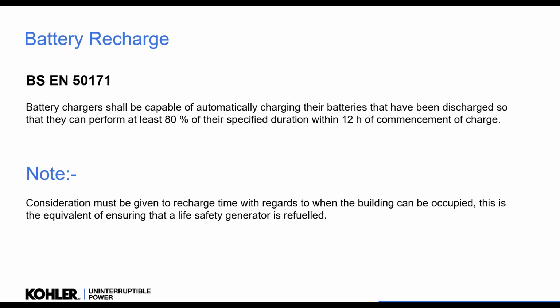50171 talks about having the batteries recharged to 80% in 12 hours. Okay. We need to consider that recharge time of the batteries. If we are going to do a full discharge test every, maybe once or twice a year, we have to make sure that that battery is recharged before we can enter the building. Otherwise, we haven't got the battery. It's not like a generator that can just be refueled, or the tank twice the size to have that time. So we have to consider that, and it's not often considered. Okay.